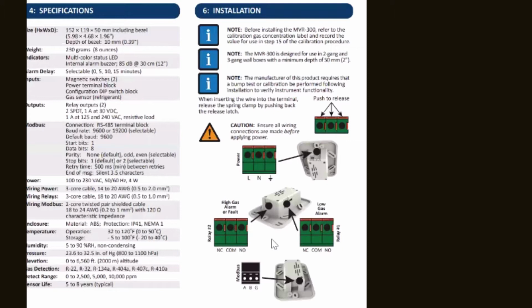Now, as we get into the controller, Mike, you'll see that there is also a higher level alarm contact that you may be able to use as well. Maybe it goes to a fire panel or something. Sure. So I like that, but the controller itself, are all these devices addressable? In other words, will the controller know which room the alarm went off in? Absolutely. Okay, so I probably don't need to tie to my patient station. I can tie my nurse call right to the controller.